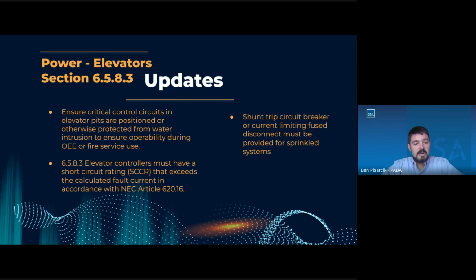And 6583, elevator controllers must have an SCCR rating that exceeds the calculated fault current. This is a code requirement. We don't like to repeat code requirements, but we do like to draw attention to them where we think there may be issues, where it may be getting overlooked and that sort of thing. So that's why we included that. It's our understanding that there's not a lot of higher rated elevator controllers out there, and we want to make sure that we get what we need for code.